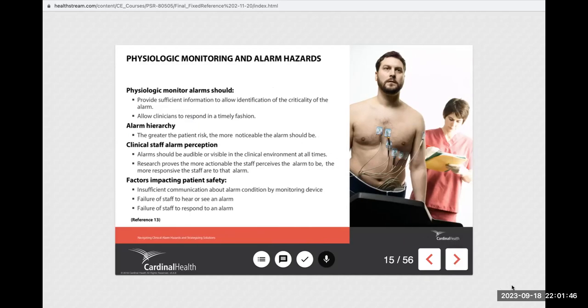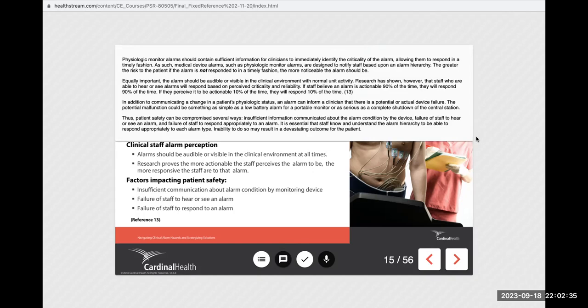Physiologic monitor alarms should contain sufficient information for clinicians to immediately identify the criticality of the alarm, allowing them to respond in a timely fashion. As such, medical device alarms, such as physiologic monitor alarms, are designed to notify staff based upon an alarm hierarchy. The greater the risk to the patient if the alarm is not responded to in a timely fashion, the more noticeable the alarm should be. Equally important, the alarm should be audible or visible in the clinical environment with normal unit activity. Research has shown, however, that staff who are able to hear or see alarms will respond based on perceived criticality and reliability. If staff believe an alarm is actionable 90% of the time, they will respond 90% of the time. If they perceive it to be actionable 10% of the time, they will respond 10% of the time.